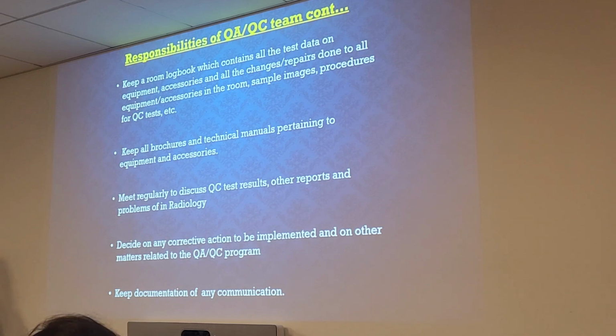The second one is very important. You want to make sure that you keep all brochures and manuals in each x-ray room, CT room, or whatever. Brochures and manuals come with the x-ray equipment when it's installed. Those are to stay in the room, they're never to be removed, because a lot of those manuals are actual guides on how you perform the QC test on that particular equipment.